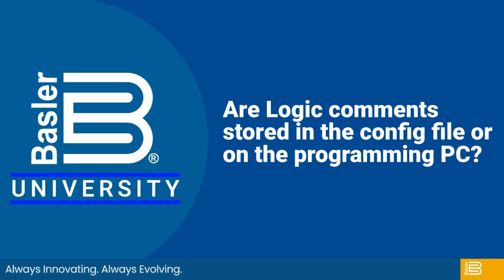So in the BestCom software, as you're building it on your offline system, you can download both the configuration file or the logic file separately, or there is also a tab to download both of them. So all of the logic and all the configuration are stored on the DGCs. It's just making sure that you load them to that DGC either simultaneously or in two different steps.